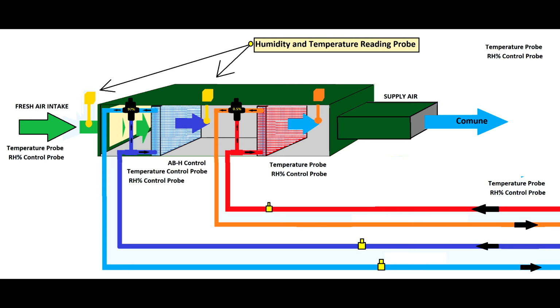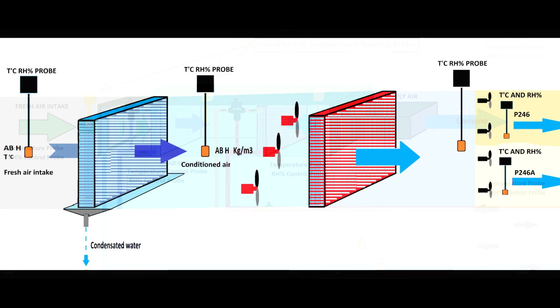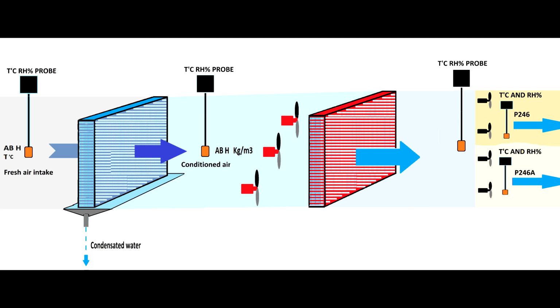This is an image of an air handling unit. You bring air to one side, the air passes by two heat exchangers, and continues its journey to cool the premises. If you have multiple rooms without reheaters or recoolers, it's obvious that if the rooms are not well calculated, you can have different temperature and humidity in any of these rooms, because this HVAC controls the global air flow temperature and humidity. Like in this situation, you can have good control, so you'll know the temperature and humidity value of the air when it leaves the air handling unit, but when the air reaches the rooms, you will provide the same temperature and humidity for any of these rooms.